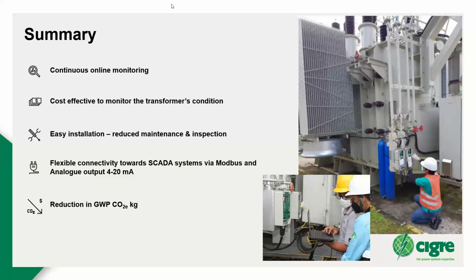Yeah, I would make a comment. Actually, this is very good. Generally it's like that - we talked about the danger of moisture. The first and worst danger of moisture is that you get low breakdown. If you have online drying, the first thing your online instrument or device does is dry the oil. This gives you the possibility to operate the transformer further. Depending on the device, it can take more water when the transformer is warm, so that's always there.